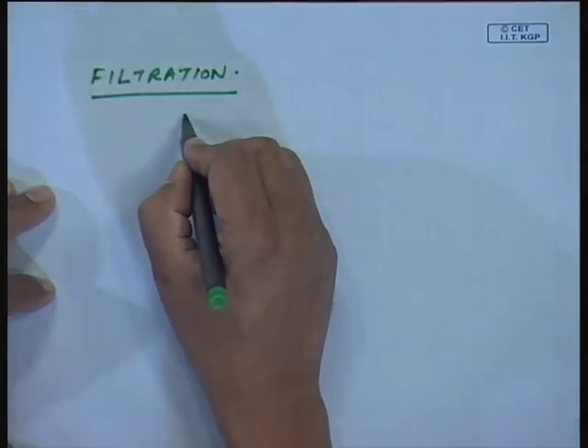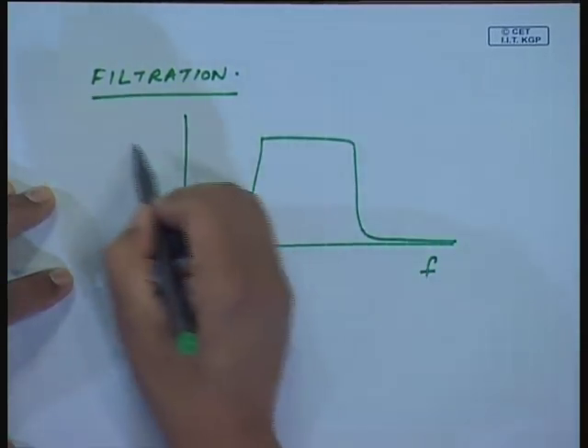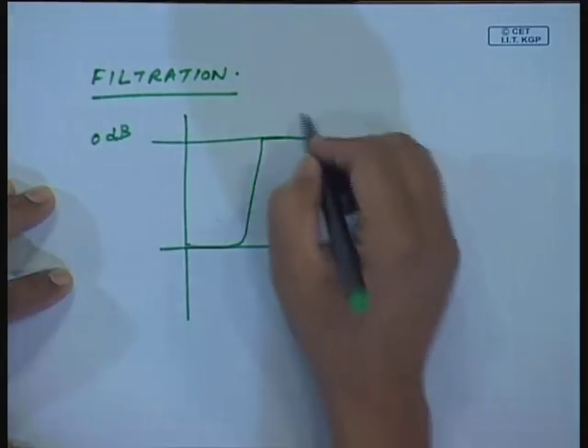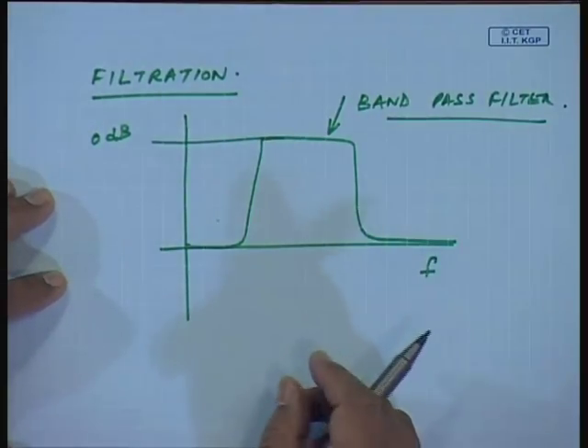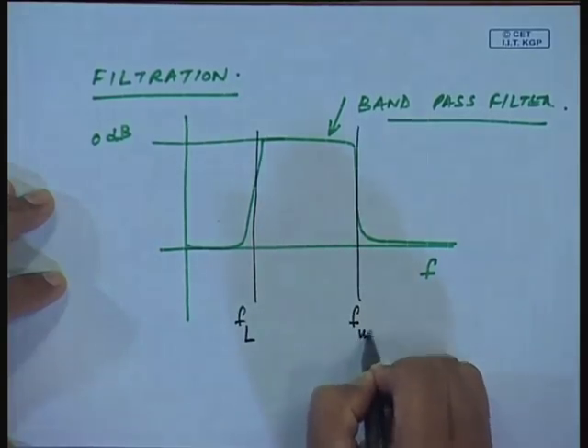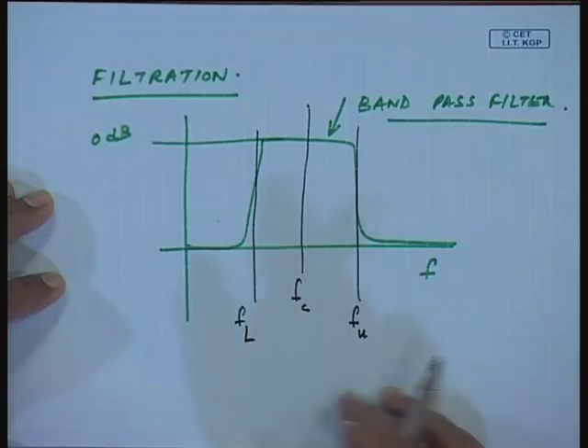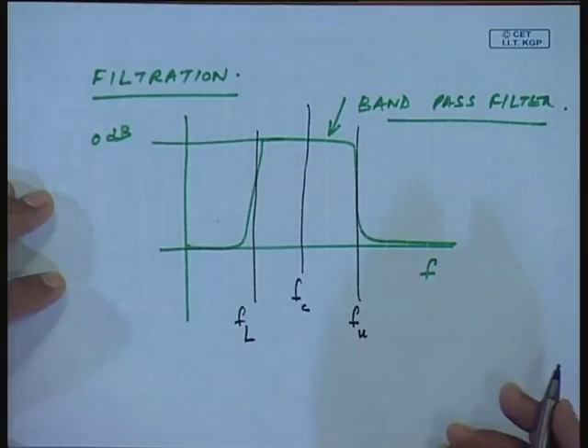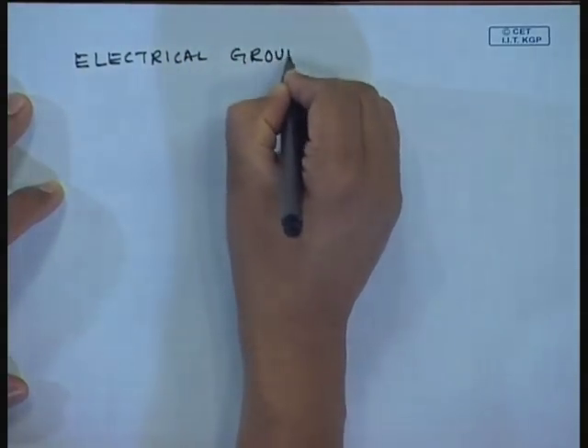Using a band pass filter with a lower frequency F_lower, upper frequency F_upper, and center frequency F_C, we can eliminate out-of-band noise. Depending on your understanding of filters — whether an octave filter, one-third octave filter, linear band pass filter, or notch filter — we can choose appropriately. Particularly when doing measurements in mechanical systems with an electrical power supply, there is a problem known as an electrical ground loop.